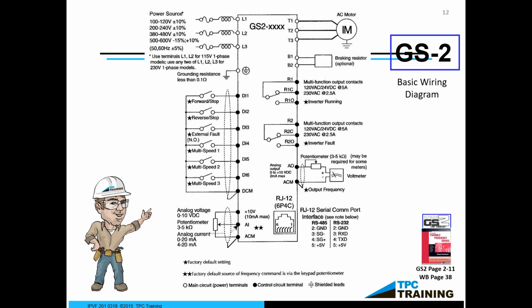If we're going to go a great distance, we certainly use a 4 to 20. For the short distance, I'm talking about where the sensor is or where the tank is as opposed to where the drive is. So with 4 to 20, you can go 1,000 feet. A 0 to 10 volt signal, we'd want to keep a little bit closer. So you can tell on the left side how to control this: forward stop, reverse stop, external fault, multi-speed. That means a dedicated speed. You hit that switch, you want it to go 14 hertz. Perfect. We can set it up for that.